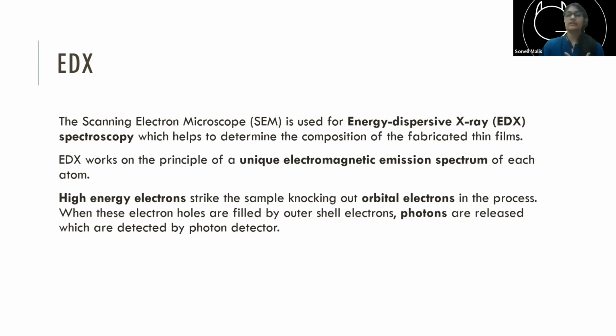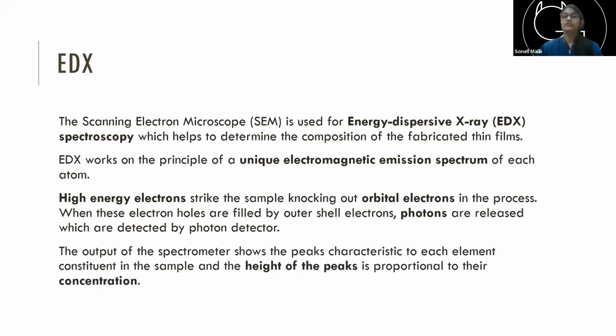Because the electron is losing some energy, it will release a photon. That photon is detected by a photon detector, which can measure the energy of the photon and also the number of photons detected for the same energy. So at the end of the day, you bombard a lot of electrons and collect a lot of photons emitted from your sample, and every element has a unique spectrum. We know the exact energy of a photon that will come when an L shell electron is knocked out from, say, molybdenum and replenished by the M shell electron in molybdenum itself. All of these are noted, and there is a code written to determine that if this is the set of photon energies you get, then it will be this particular material. And similarly for all other elements.